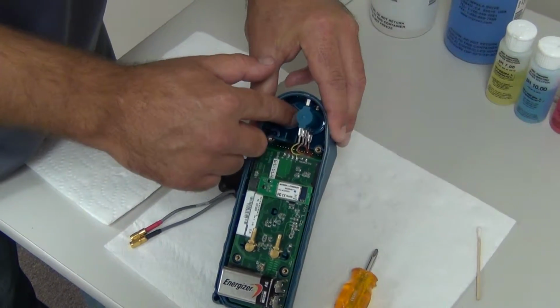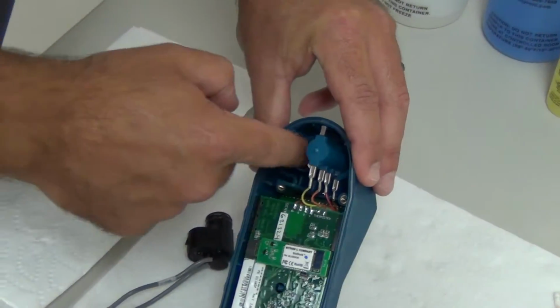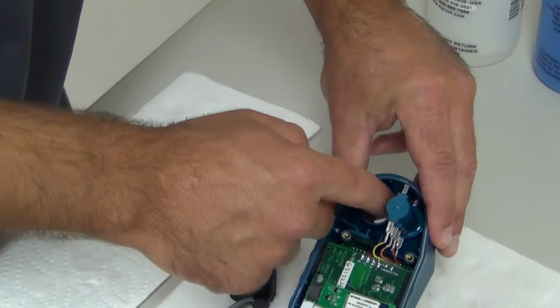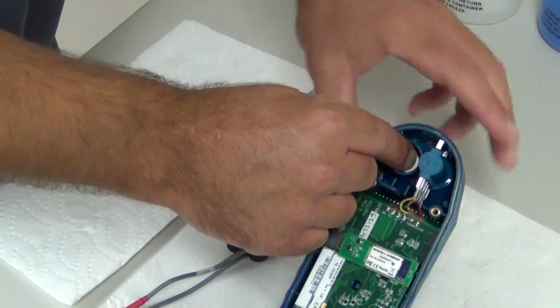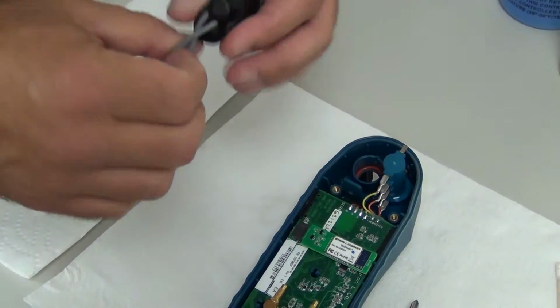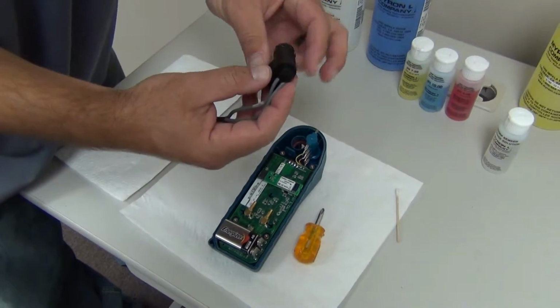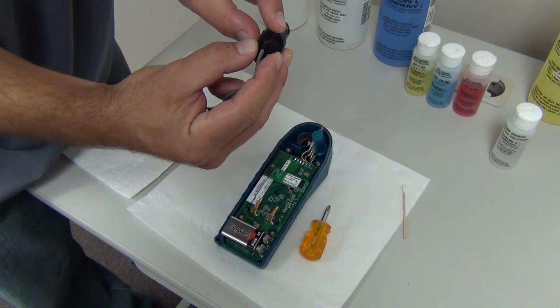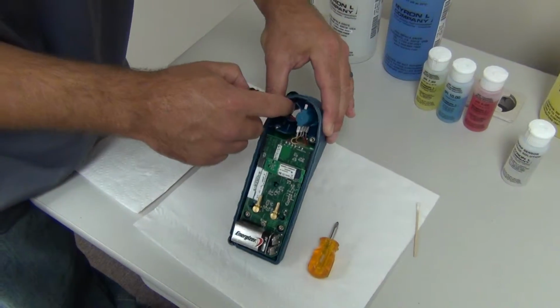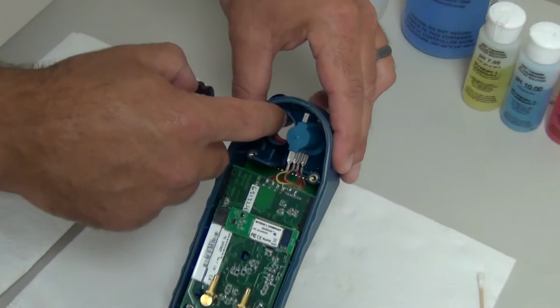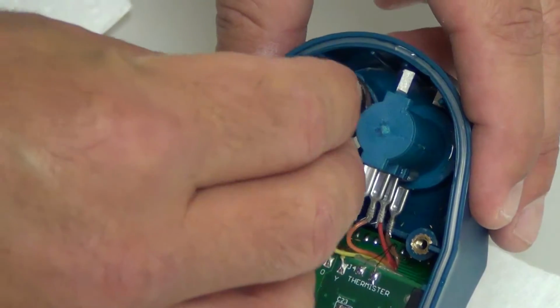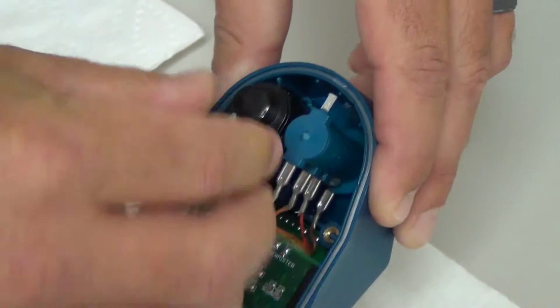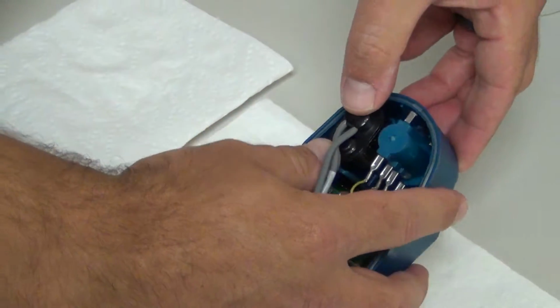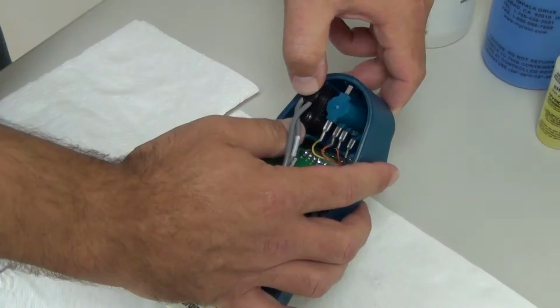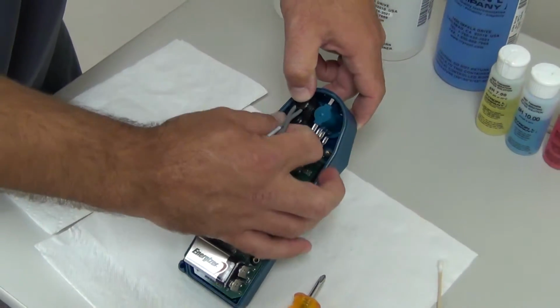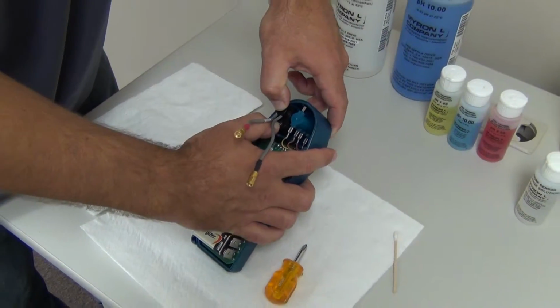First, use your finger to guide that orange O-ring down into the cell cup. On the sensor itself, you'll notice a ridge across the top, as well as a groove where the sensor will sit. Line those two up, and using the base of your palm or thumbs, press the sensor straight down until you hear an audible click, signaling that it's locked the sensor in.